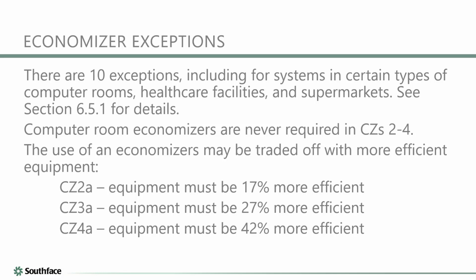But keep in mind, what I just talked about was that efficiencies are kind of going up across the board. And then you compound those higher efficiencies with even more efficient equipment because you're trying to be exempt from the economizer. So you might end up with a much more efficient unit, which is great in the long term, but obviously is going to be very cost prohibitive. So something to consider. But typically, you have to kind of balance the cost of an economizer versus that more efficient equipment.